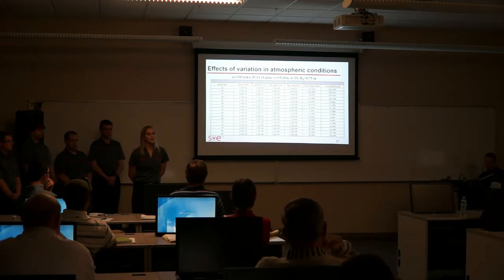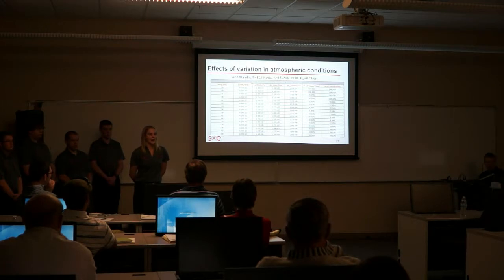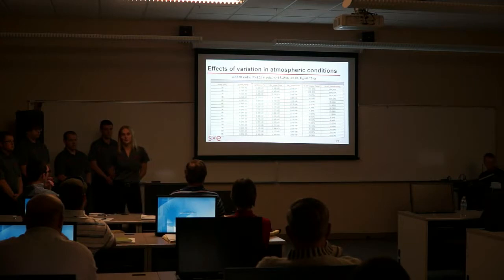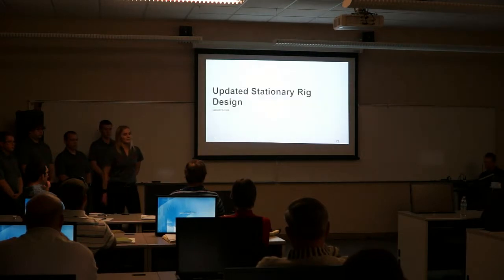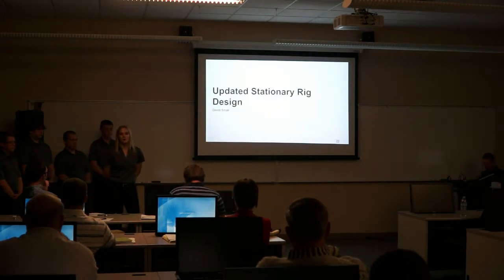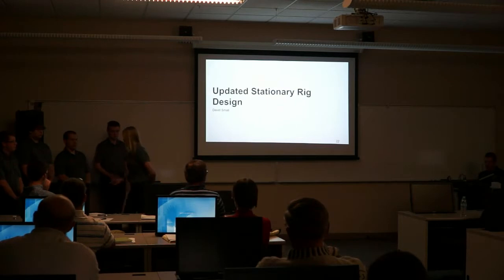The team, since we are currently undershooting the Reynolds mass flow number, has decided to optimize for lower temperatures and therefore lower dynamic viscosity. Since dynamic viscosity is a division factor in both of the Reynolds numbers, we should be able to minimize our percent difference between the given Honeywell values and the actual calculated values for those Reynolds numbers. And now I will pass it off to David Small for the updated stationary rig design.